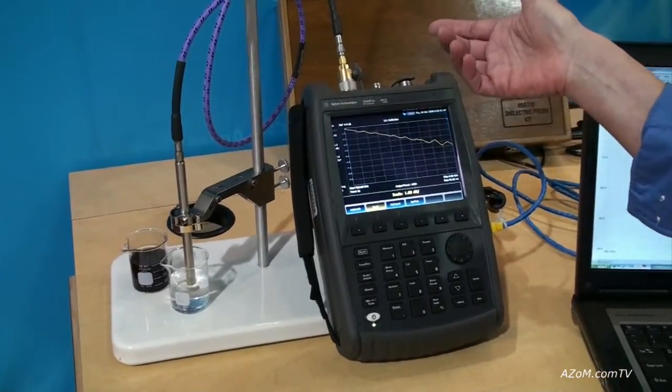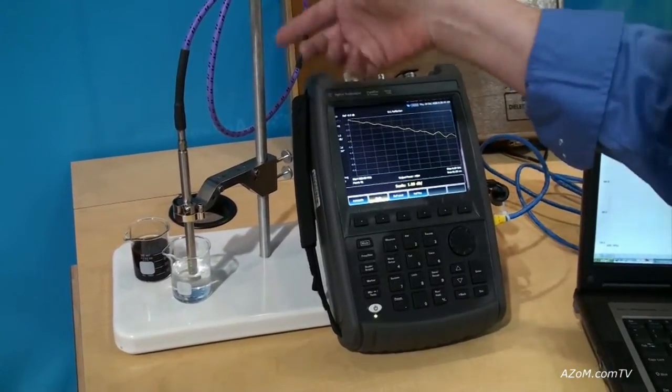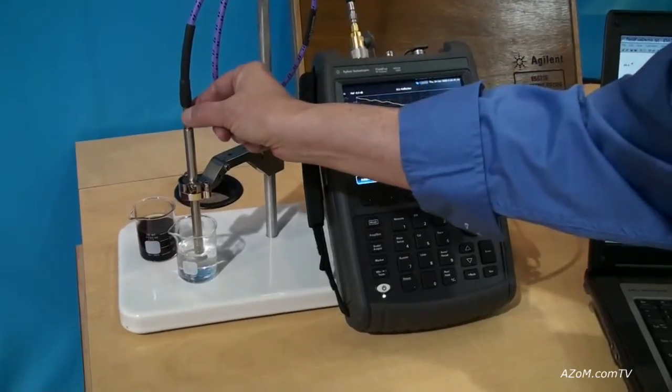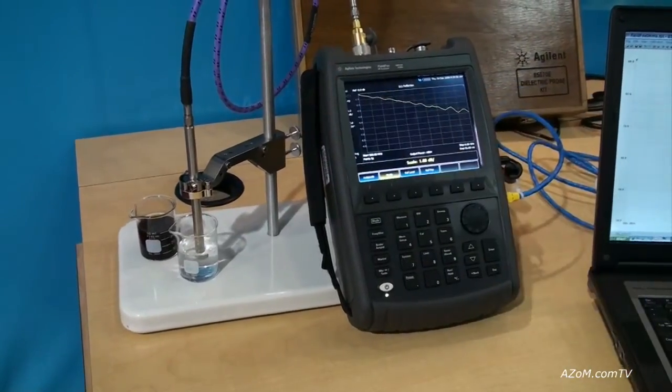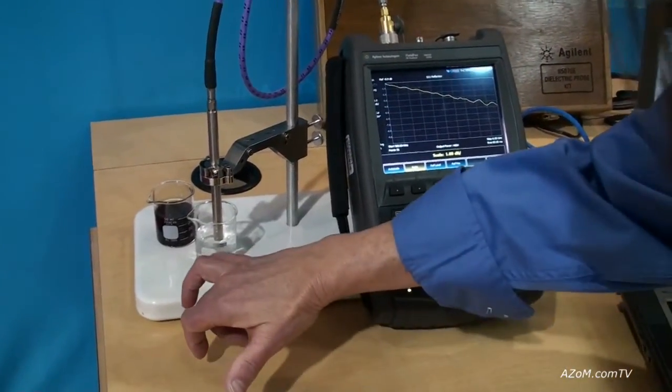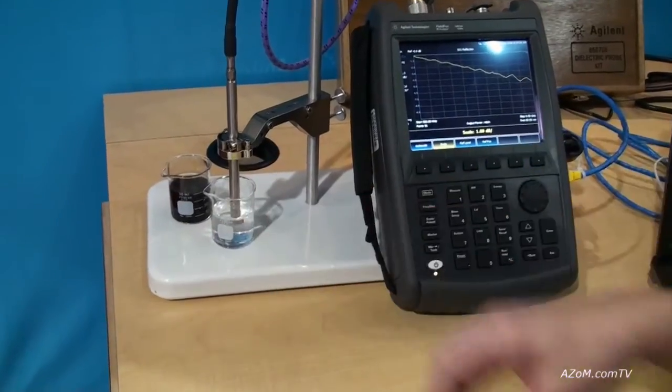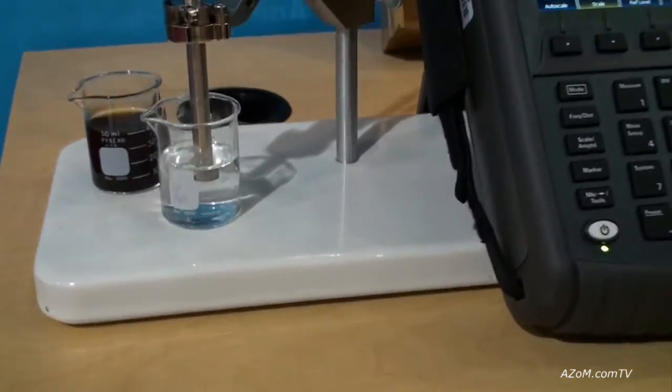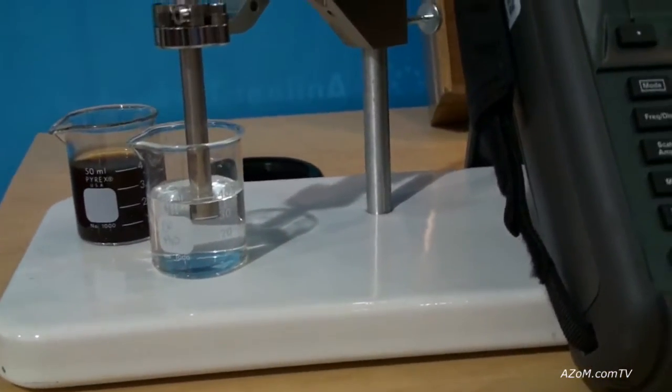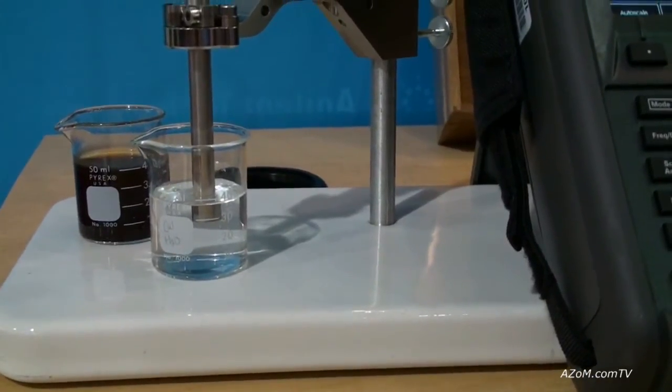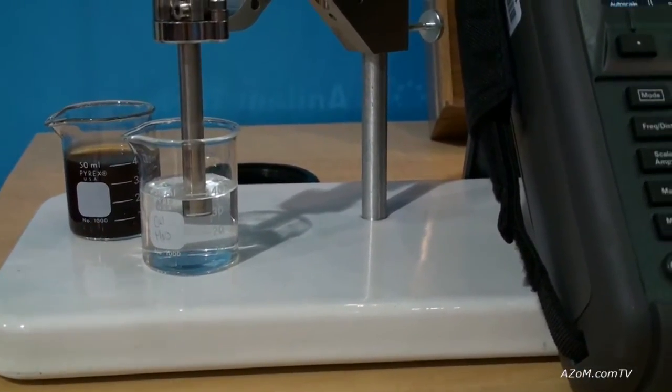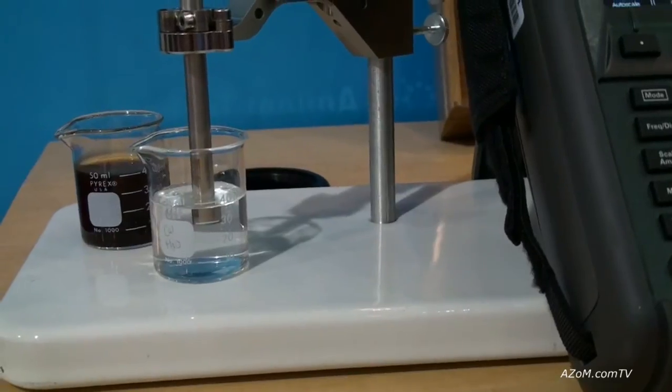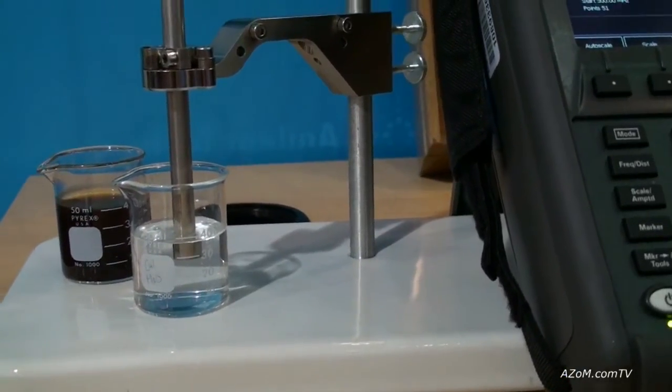We're measuring S11. Energy travels down through the cable into our open-ended coaxial probe, and at the tip of the probe, it's sealed with glass, but the field fringes out into the material, and how it reflects back is different depending on what you put the tip of the probe into.